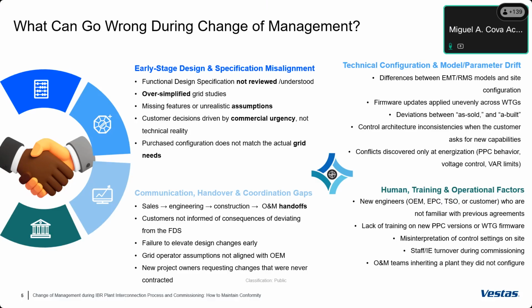The third component will be communication and handover. It's very important to have specific protocols for handover between sales, construction, and service. Also crucial is not deviating from the functional design specifications, because any deviation will require value engineering. Sometimes we observe that the way the grid code is interpreted differs between the OEM and the grid operator. This is common. There are good forums for these discussions in some regions, but in others, like parts of the US, those discussions don't take place, and there's a single interpretation from the grid operator that isn't always aligned with the OEM. I'll skip the human training and operational factors, like changes of staff or engineering consultancy firms, which also impact projects during handover or change of management.